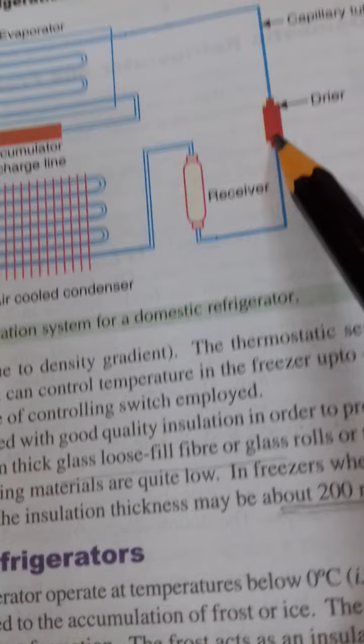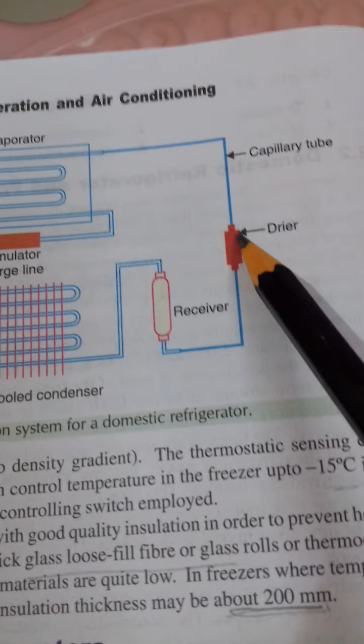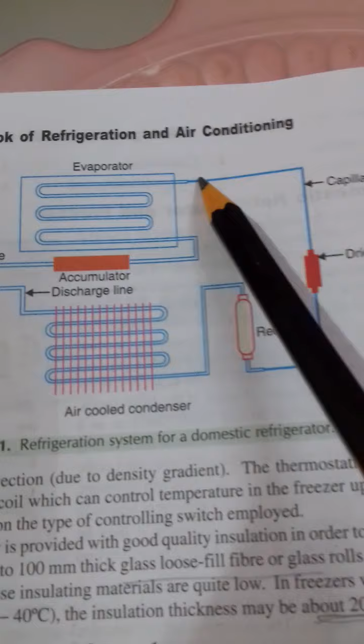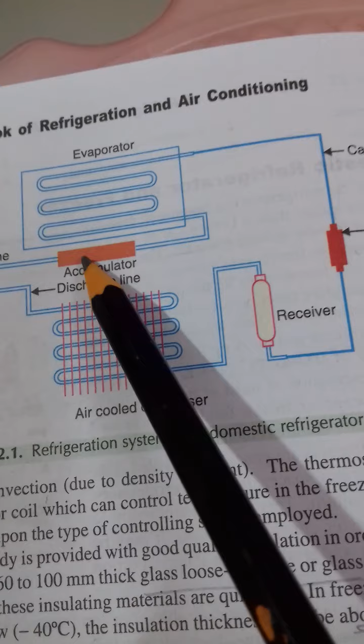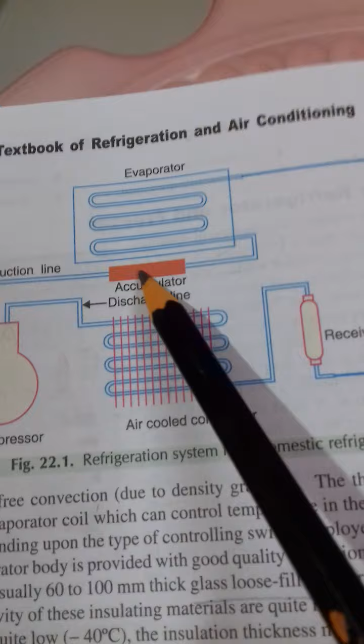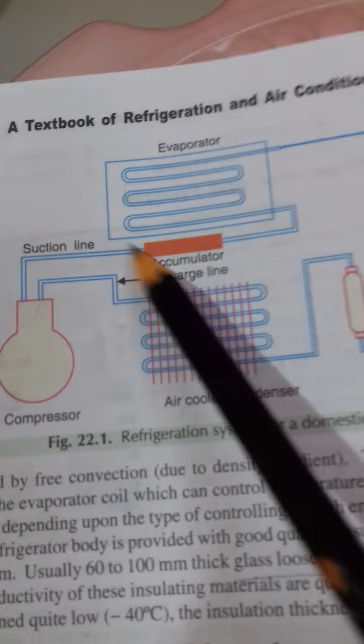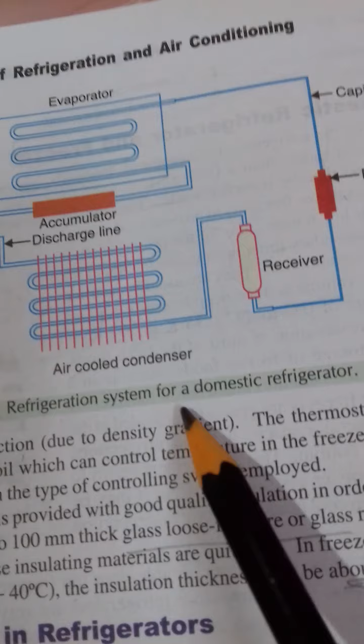After the receiver it goes to the dryer, and in the dryer, to prevent moisture from going through, silica gel etc. is kept. Then the capillary tube gives the expansion at constant enthalpy, and then it goes to the evaporator, and from the evaporator it goes to the accumulator. Accumulator means just to remove the liquid particles. If at all any liquid is coming from the evaporator, it should not be allowed to go to the compressor. So only gas is allowed to go inside the compressor. In that way the whole cycle is completed. This is your vapor compression cycle refrigeration system for a domestic refrigerator.